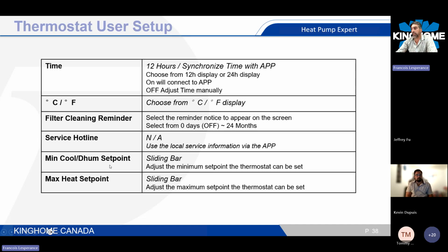Minimum cool set point is a sliding bar where you can lock the minimum set point for cooling, or the maximum heat point in heating. So basically, if you just want to make sure your customer will not go lower than a certain point, like you don't want your customer to set the thermostat at 10 degrees, for example, you want to lock that maybe at 16, 18. You have the ability to do it. Same thing for maximum heat set point. You don't want to adjust the maximum set point to 32 degrees Celsius, for example. You want to make a barrier like at 28 or 30, then you can adjust it.